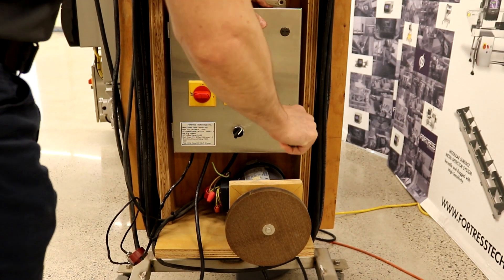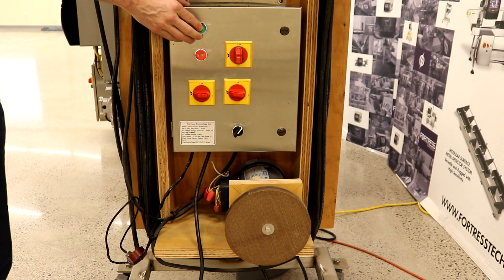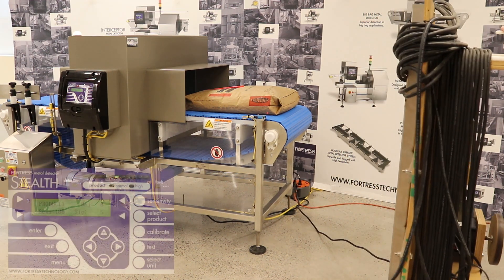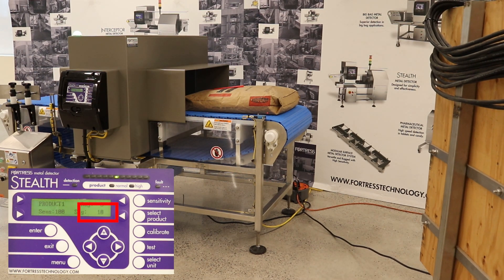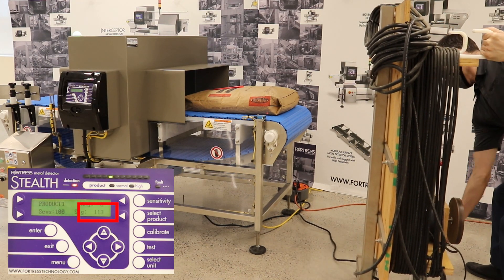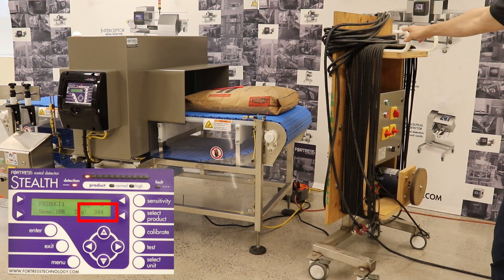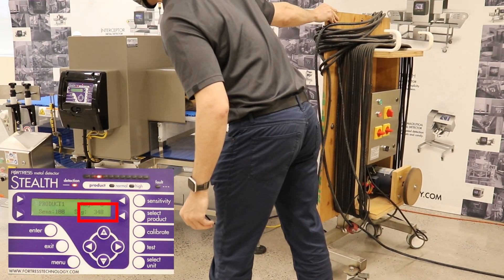We will now close the box and start the motor. Notice that the strength of the signal generated on the metal detector gets larger as the source moves closer and is more visible to the coils. The EMI is broadcast over the air and into the receiving coils of the metal detector. The worst case is when the aperture opening is in line with our noise generator, as there is a clear line of sight between the motor cable and the metal detector coils.